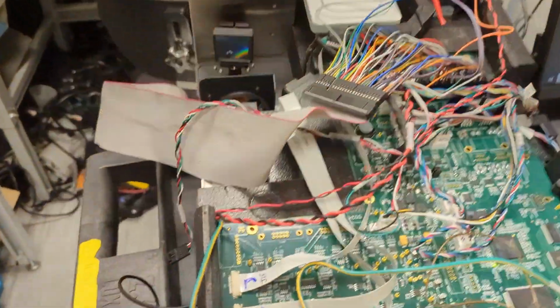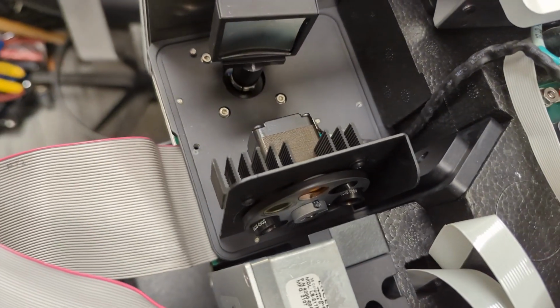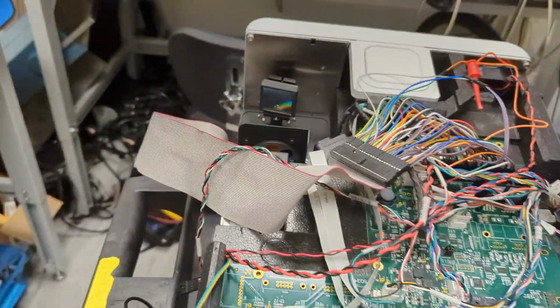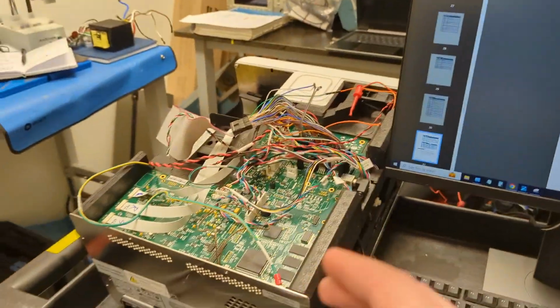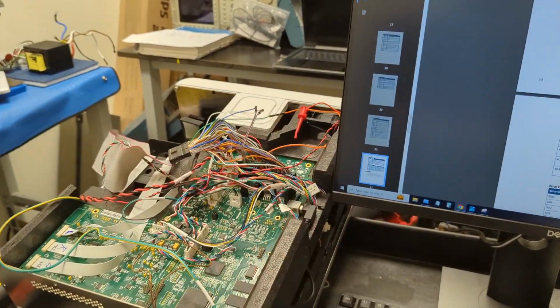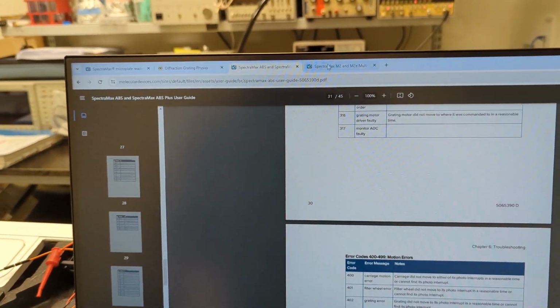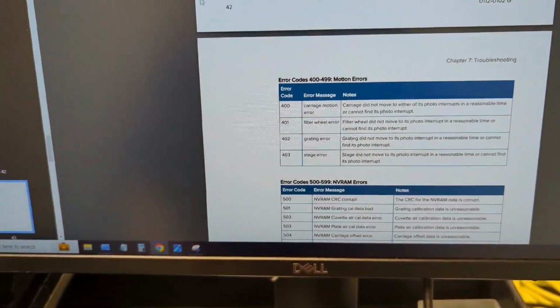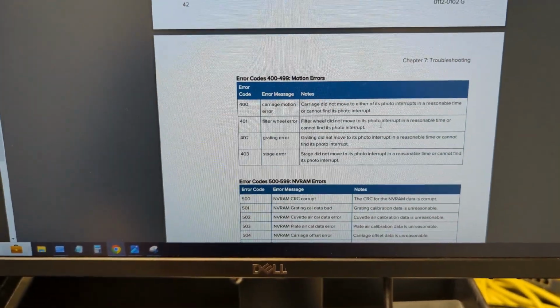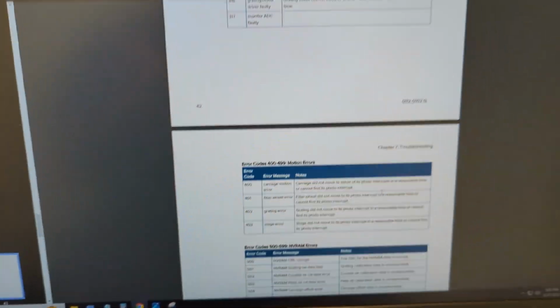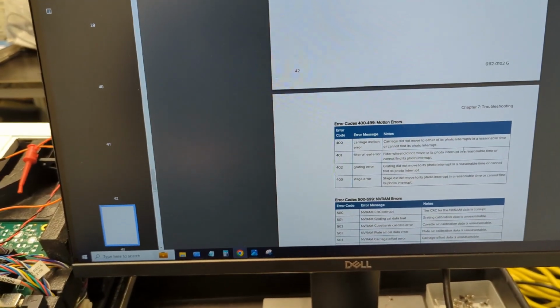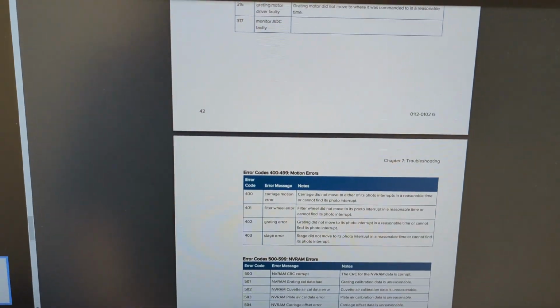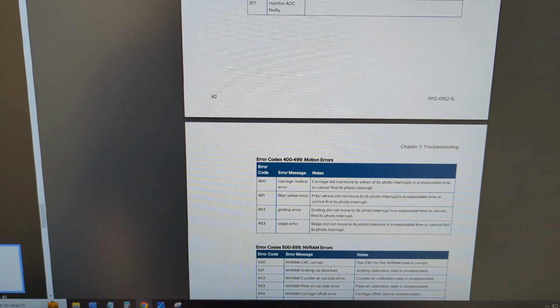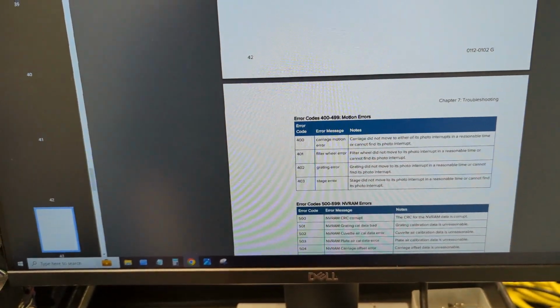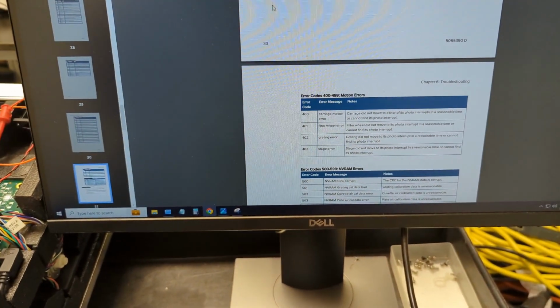Now, the problem with that is, this is the filter wheel. There is no homing sensor, okay? There's no homing sensor to be found. Now, this SpectraMax, there have been a lot of generations of this piece of equipment. We actually have one that's a lot older. This is the ABS Plus. I'm showing you a manual now for the M2. It is the exact same. You can see here, filter wheel did not move to its photo interrupt. It's the exact same description. Now, the M2's filter wheel does have a homing sensor. So, this company didn't even bother to update their error codes. It looks like I'm just switching between duplicate pages. They didn't even bother to update their error codes for a more accurate description.